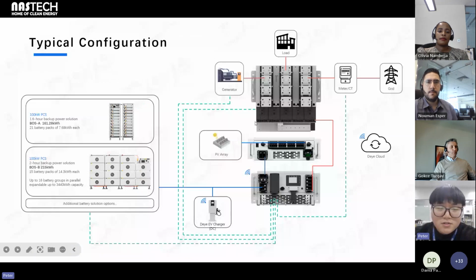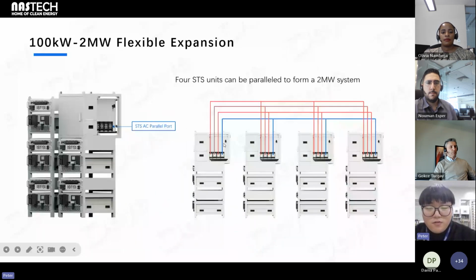We can have a BOS-A solution, which can last for 1.6 hours for backup. And the BOS-B solution can last for 2 hours for backup. And here you can connect the DC EV charger between the battery and the DC port of the PCS. For STS, you can parallel four of them together, and each of them will have 5 PCS. So in total, it will become a 2 megawatt system for energy storage.